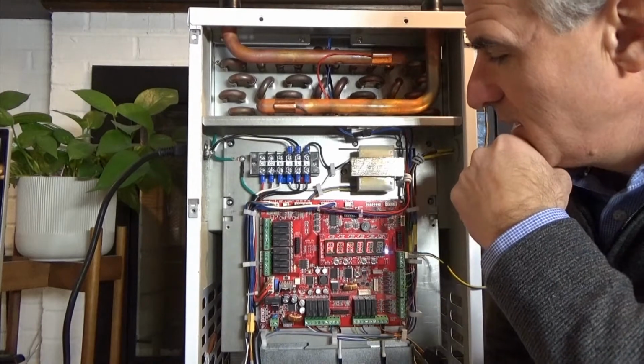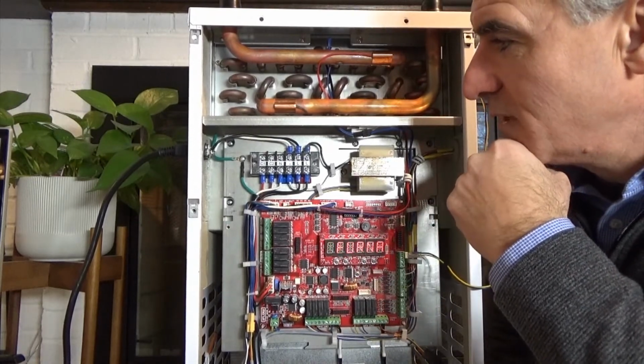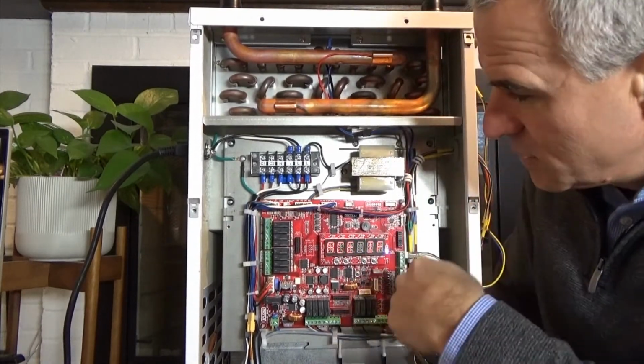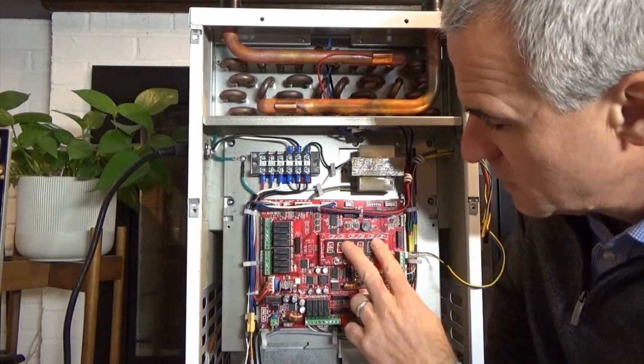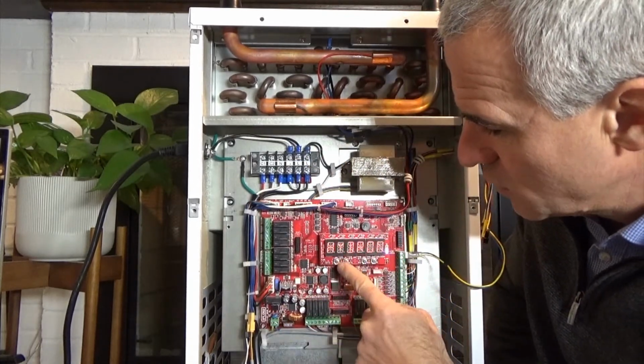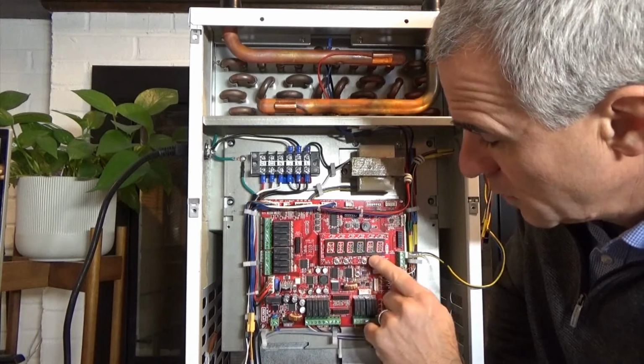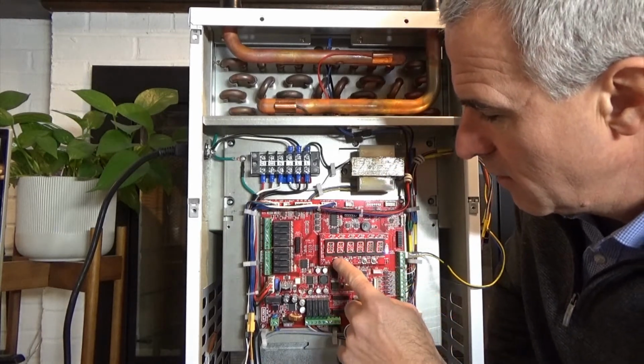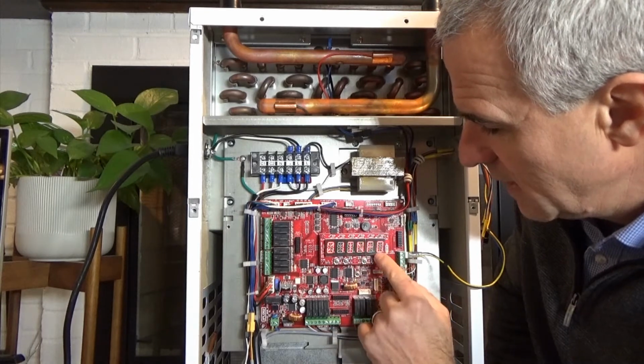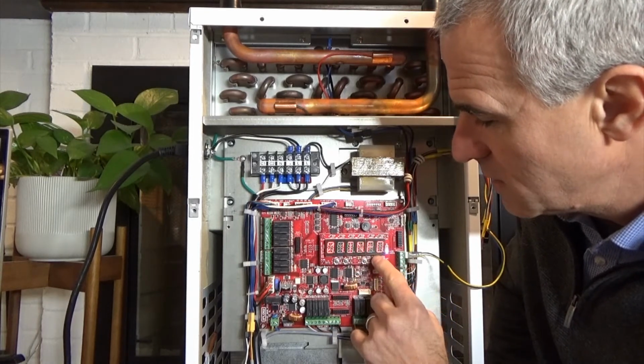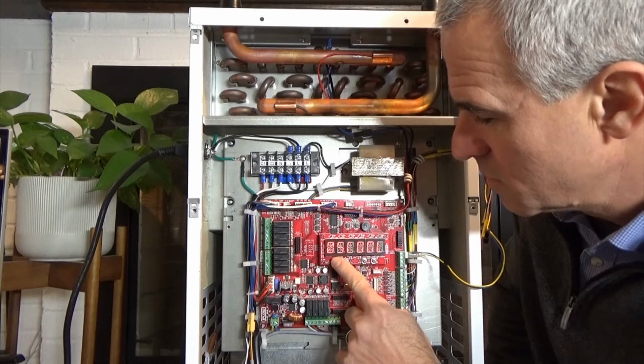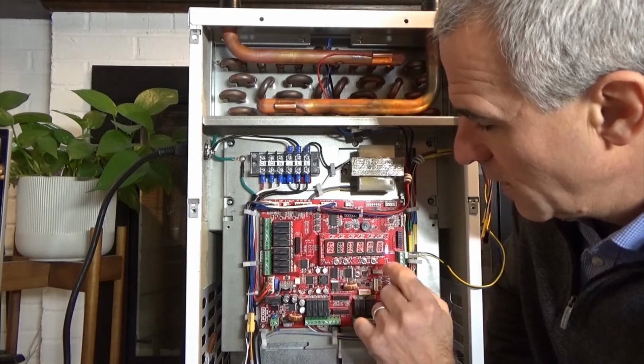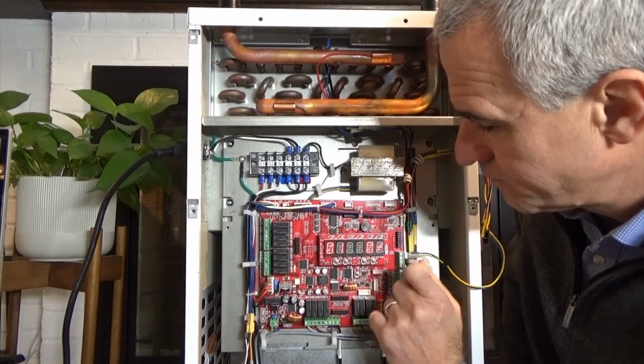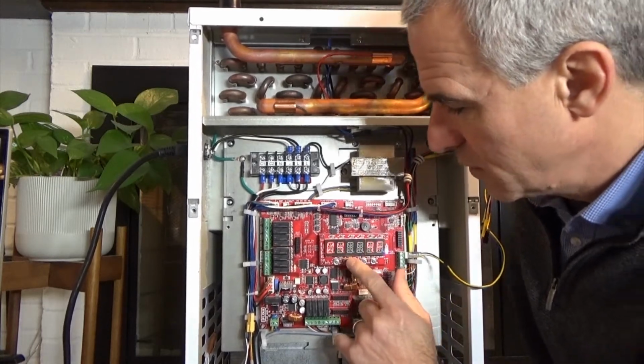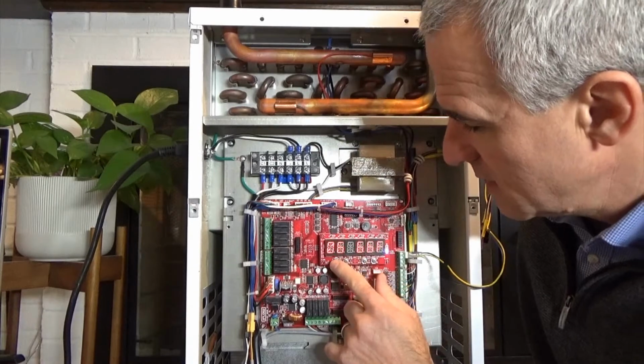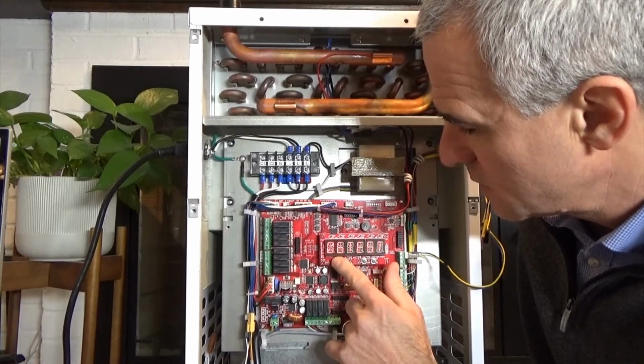So with regards to the iFLOW controller, there are a number of different components. Just a general look, you've got the display in the center, and the control for the display. You've got 4 buttons below. You've got the mode button, you've got the enter button on the right, and then up and down in between. So mode goes through the 6 modes. When you want to enter a mode, you press the enter button and then use the up and down to scroll through the different parameters in the system. So that's easy enough. That's the display.